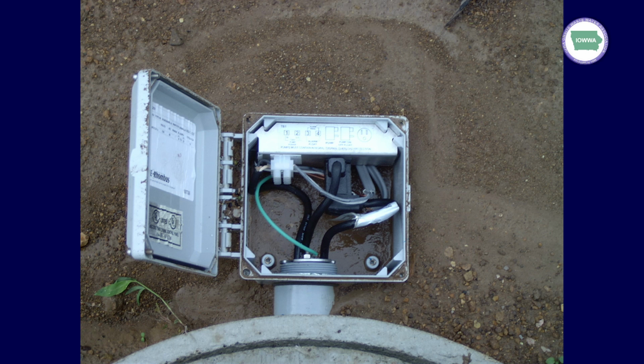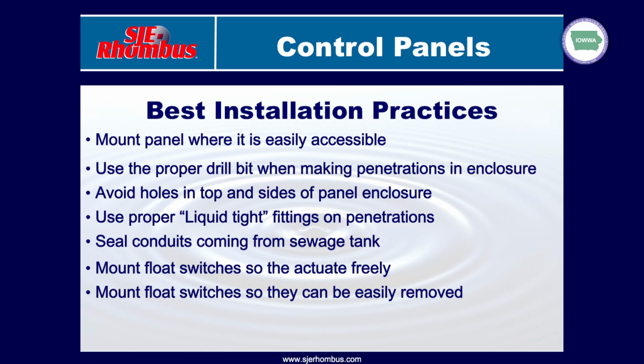So when the pump wasn't working properly, the service guy got out to the job, opened the panel door the rest of the way, and it was full of mud. So no real shock that they had problems and the system didn't work properly. All right, mount float switches so they actuate freely. You also want to mount float switches so they can easily be removed.